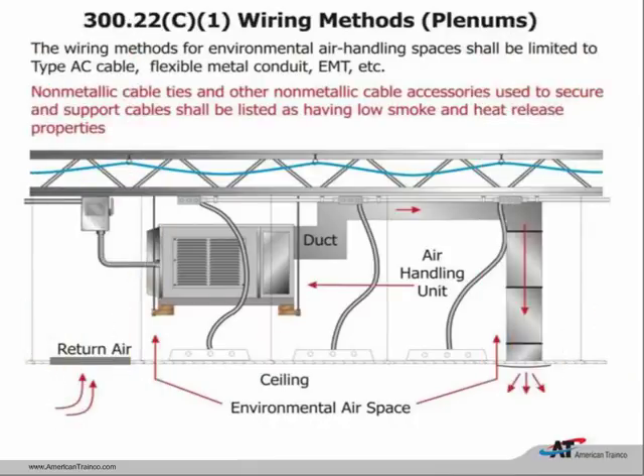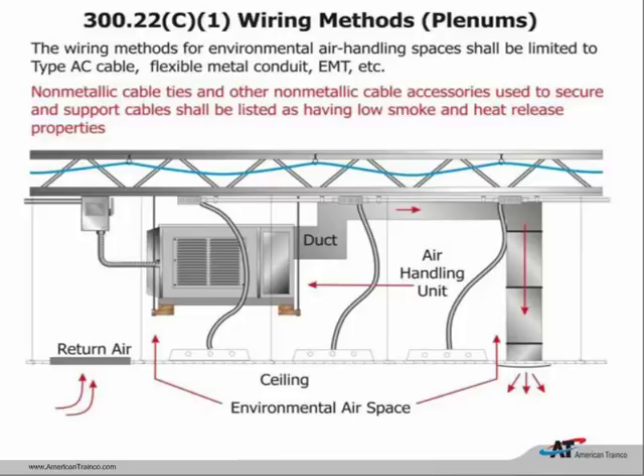Article 300 addresses wiring methods above a suspended ceiling. When a plenum uses that space for return air, we must wire with either plenum-rated cable or metallic wiring methods. Now cable ties used in plenums must also be listed, having low smoke and heat release properties. Previously you might use a clear or white tie wrap indoors or a black UV-resistant tie wrap outdoors—now there's a specific listed type for plenums.